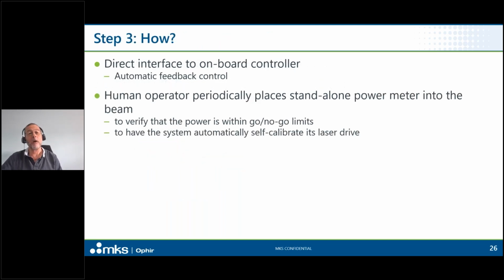Okay, step 3, how do I implement it? So for example, if I need to catch fast changes, or if I want the monitoring to be fully automated without needing a human operator, the sensor might have a direct interface to the onboard controller, let's say by using RS-232 or USB or Ethernet communication, and its readings of power could be used to provide feedback control so that fluctuations in laser power can be automatically corrected. Alternatively, in some applications where the expected unwanted drifts in critical laser parameters are much slower, it might be enough for a human operator to simply place a handheld standalone power meter into the beam once a day, for example, just to verify that the power is within go, no-go limits, or once every X time to have the system automatically self-calibrate its laser drive.